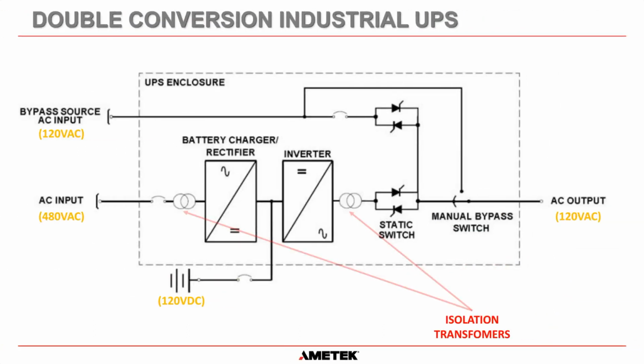So here is the one-line diagram for a double conversion industrial UPS. And I know, once again, I hate big, long words because it tends to make things a little more complicated than they should be. But when we say double conversion, what we're saying is that we convert the power twice. In other words, we change AC to DC in the battery charger rectifier, and then we change that DC back to AC in the inverter. So that's why it's called double conversion. We change the power twice.